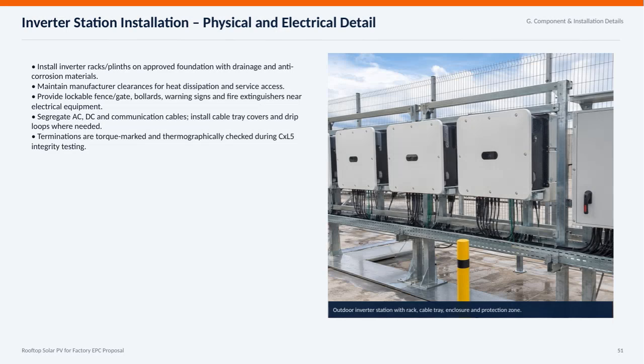Here, we focus on the installation details of the inverter station, both physical and electrical aspects. The inverter racks or plinths must be installed on a properly approved foundation that includes drainage and anti-corrosion measures to ensure durability and safety. It's crucial to maintain the manufacturer's recommended clearances for heat dissipation and easy access during servicing.